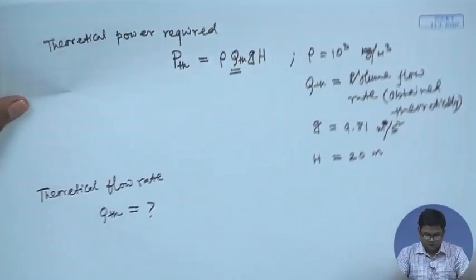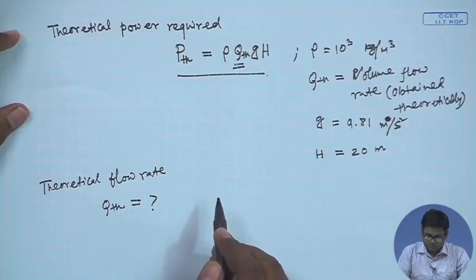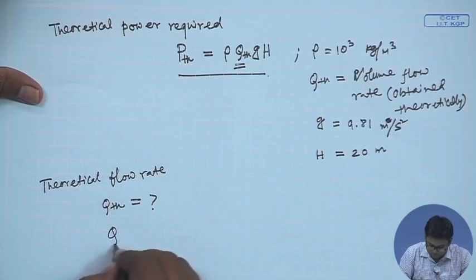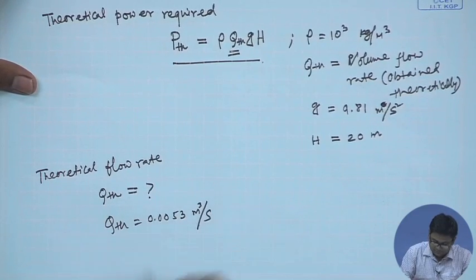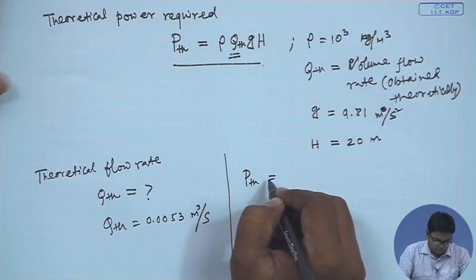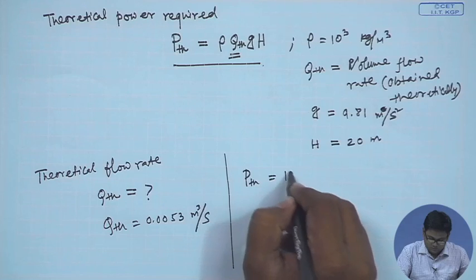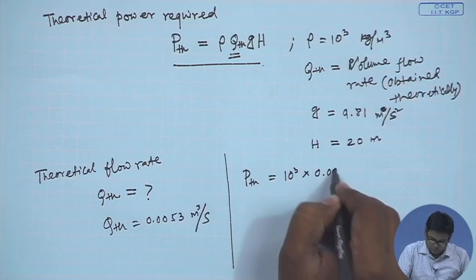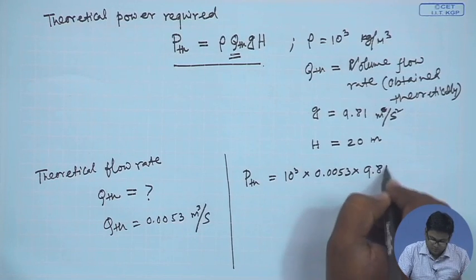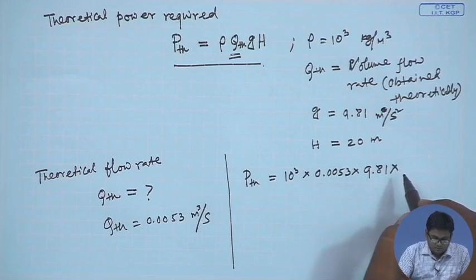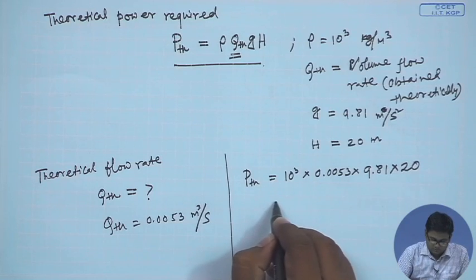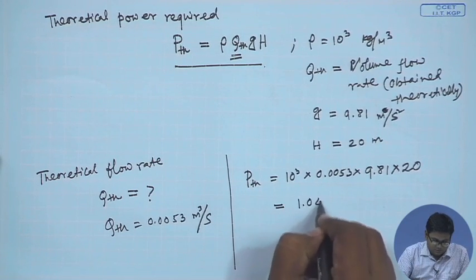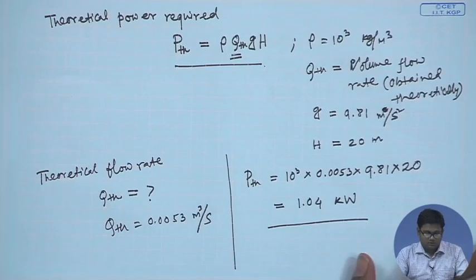Now let us find the power required. Theoretical power P_th = ρ × Q_theoretical × g × h. Substituting ρ = 1000, Q = 0.0053, g = 9.81, and h = 20 meter, we obtain P_theoretical = 1.04 kilowatt.